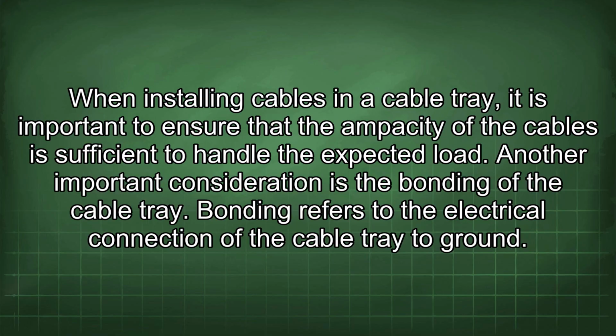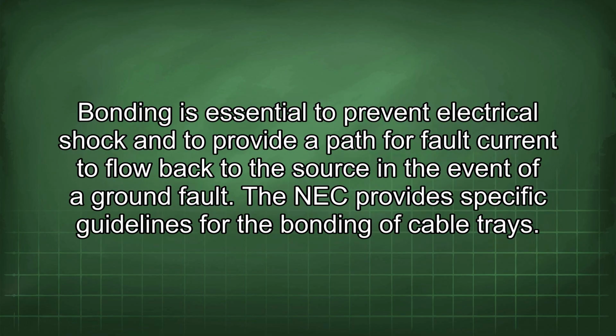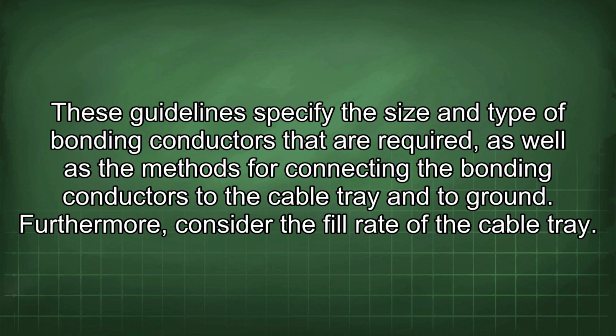Another important consideration is the bonding of the cable tray. Bonding refers to the electrical connection of the cable tray to ground. Bonding is essential to prevent electrical shock and to provide a path for fault current to flow back to the source in the event of a ground fault. The NEC provides specific guidelines for the bonding of cable trays. These guidelines specify the size and type of bonding conductors that are required, as well as the methods for connecting the bonding conductors to the cable tray and to ground.